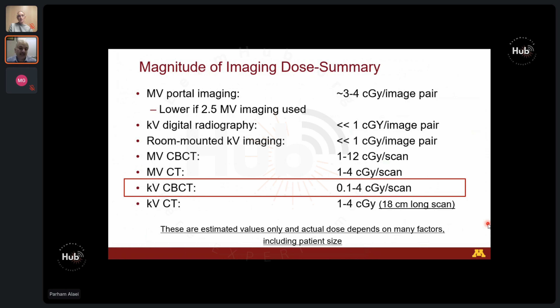And the kV cone-beam CT, I highlight that because that's what we use most of the time. So to focus on kilovoltage cone-beam CT, there are a lot of factors that affect the imaging dose or the dose imparted to the patient. Tube current: the higher the mA, the higher the dose, as a linear relationship. Applied voltage: higher kVp is a higher dose, by kVp squared. Multi-filter reduces the dose in general. Start-stop angles on a partial imaging actually help with avoiding imaging some of the organs at risk, potentially reducing the dose. The blade setting or cassette size affects the image volume in the cranial-caudal direction, head to toe.